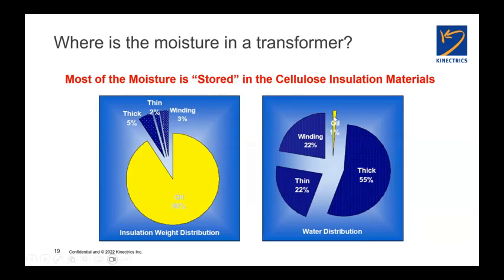Growing up, we're always taught water and oil don't mix, and fundamentally that's a true statement, but at a molecular level, there is some dissolving of water in oil, but it's very, very small. So even though oil is 90% of the weight of the transformer, only 1% of the moisture is actually in the oil. It's in the parts per million range, right? All the water is in the paper and the press board. And this is where the problem starts to come when we talk about removing moisture from a transformer. It's actually very easy to remove moisture from the oil, but that's not where the water is. The water's in the paper, and it's really hard to remove the water from the paper. That's the gist of it.